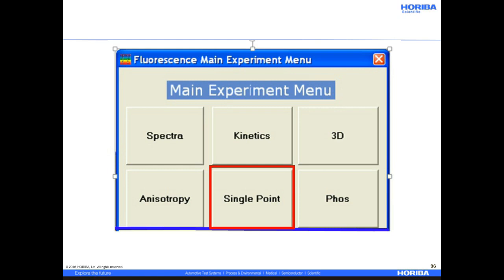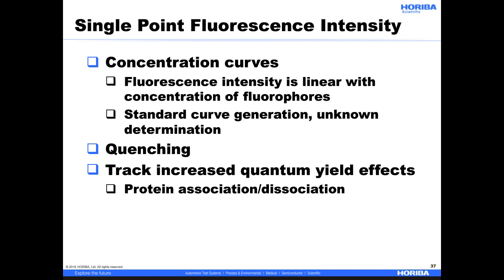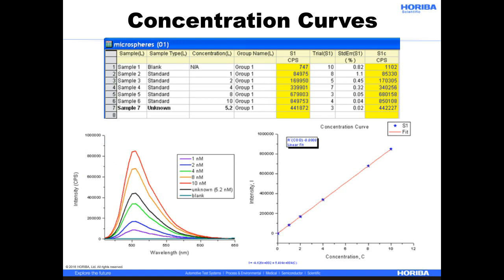Next, we will discuss fluorescence single point measurements. Because fluorescence intensity is linear with the concentration of a fluorescent molecule, standard concentration curves can easily be generated and used to determine concentrations of the same molecule in an unknown sample. This is useful in quenching experiments where additives decrease the intensity of the fluorophores in a systematic way. Concentration curves can also be created to study how other molecules interact with proteins, and can be used for tracking protein structural changes systematically. As an example, here is a calibration curve of a known set of fluorescent microspheres or beads. Five known concentrations were used to create the standard curve, which was then fit and used to calculate the concentration of beads in an unknown solution.